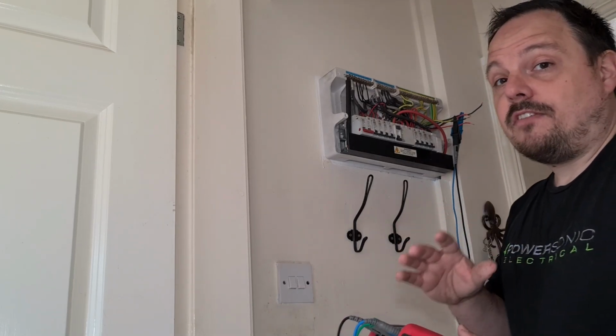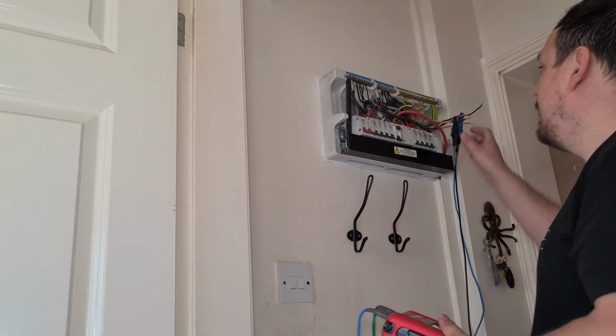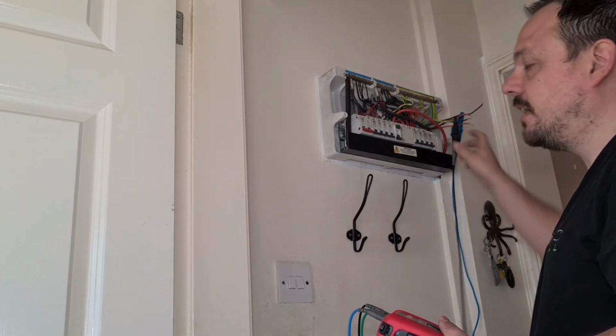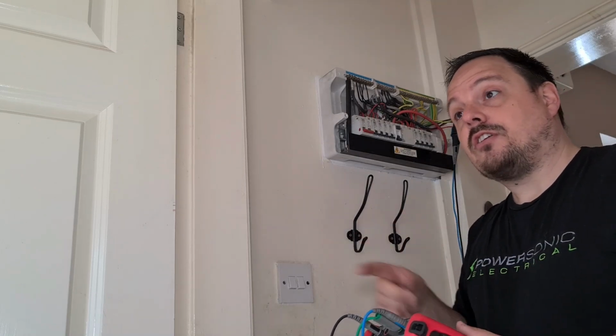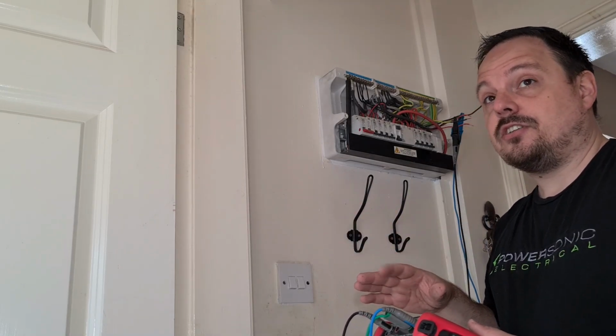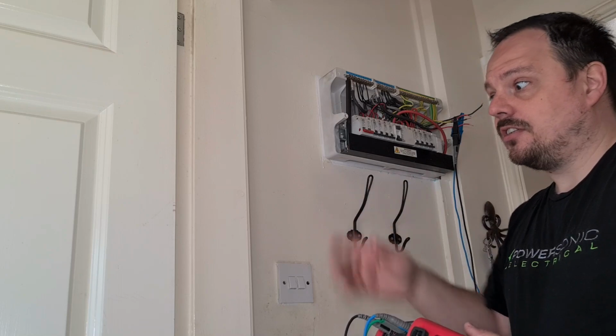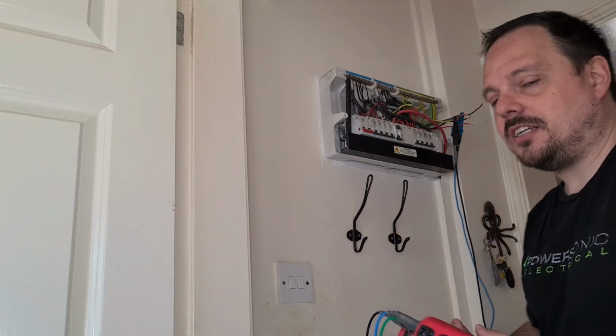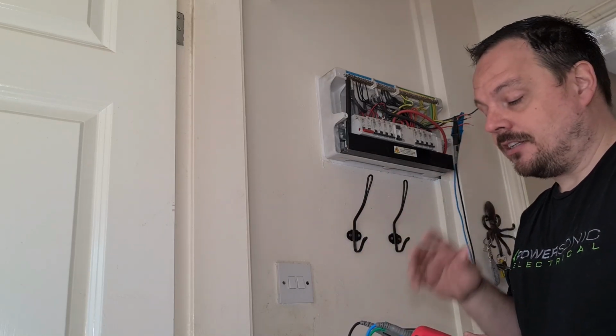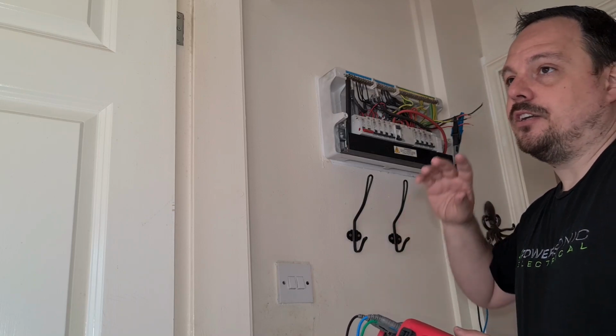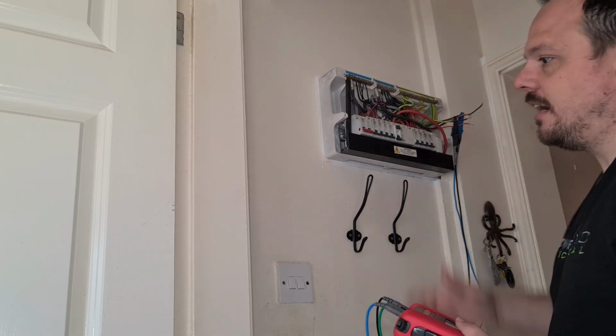Again there will be some variation, the way the cables are dressed. These are all a pretty similar length inside the consumer unit, but some of the sockets might have a different way the terminations are connected together, with longer and shorter lengths of your lines and CPCs. So you need to keep that in mind - it's not going to be exact, 1.67 times, and your R1 and Rn being the same. It's just not.